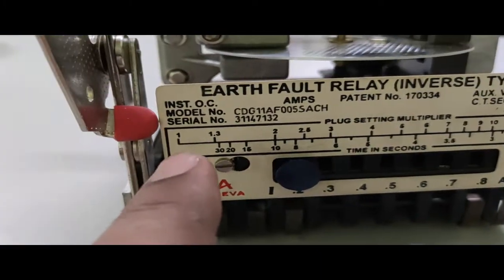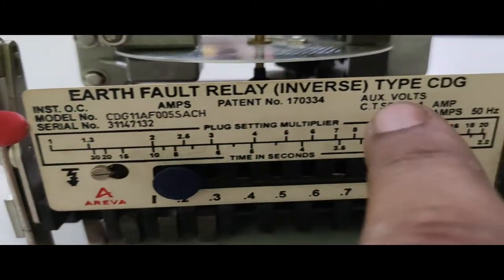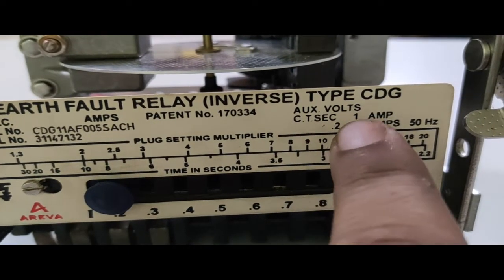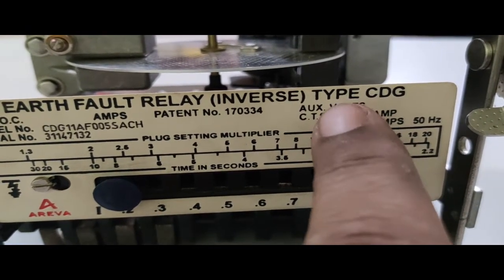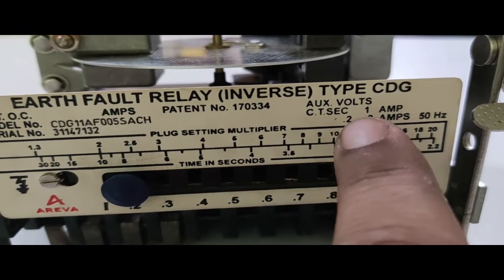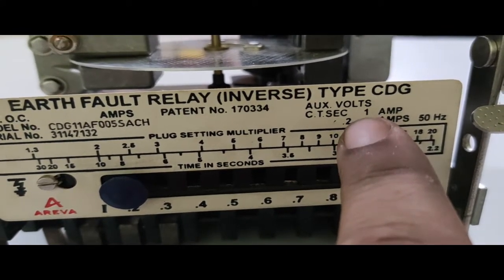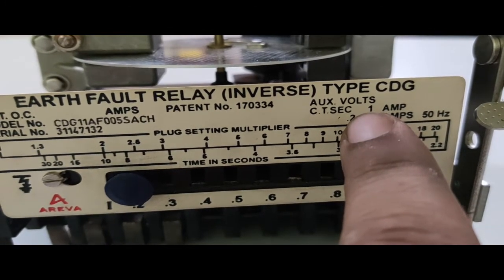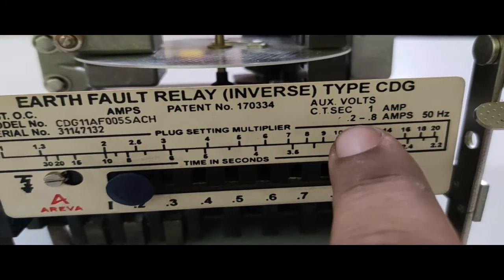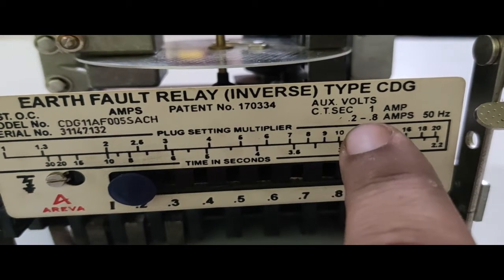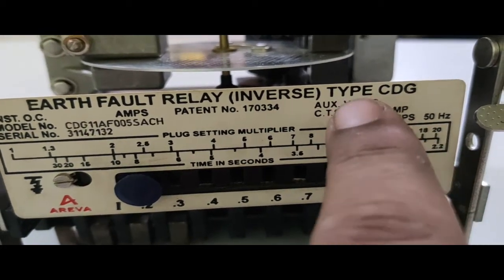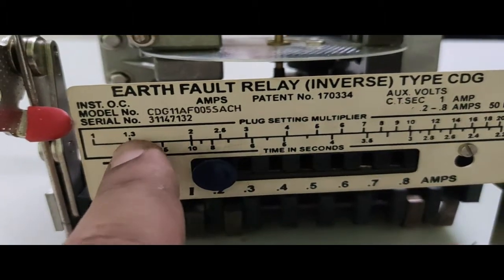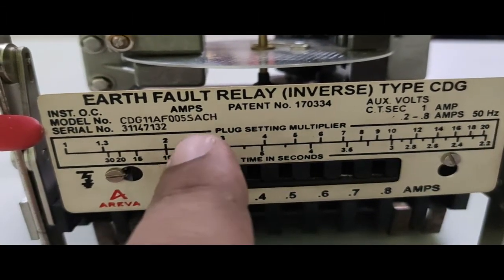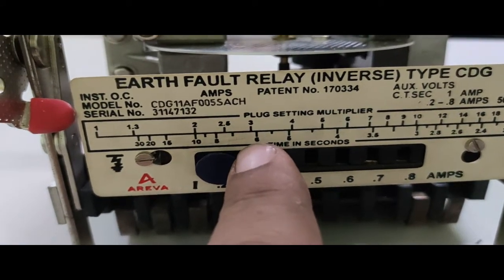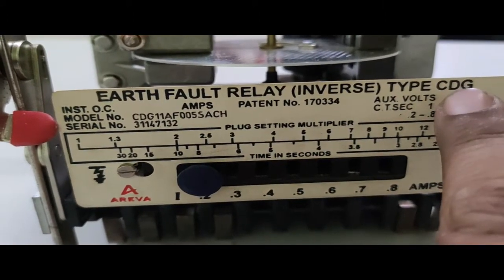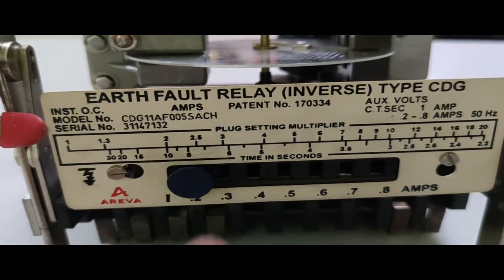Now this is the model number, serial number, auxiliary voltage, CT secondary, here it is 1 ampere. That means the relay should be powered through a CT, because the relay is a low power device and it should be connected to a CT whose secondary current should be 1 ampere. And the relay can be operated at 0.2 to 0.8 amperes, 50 hertz. This is the current characteristics of the relay. Here you see a table. This is nothing but the plug setting multiplier versus the operating time of the relay. When I explain the IDMT characteristics of the relay, you will understand these things better.